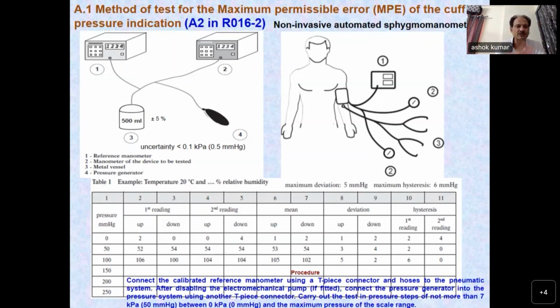If you Google it, you will find the R16.1 and R16.2 PDFs available on the web page. Everybody knows you have to follow all 20 parameters for type approval, including electricals and other parts. So this is one way. Another way is to have the automated device and another reference pressure gauge, with a known volume, like the 500 ml already defined, with plus or minus 5% error or uncertainty, and you can generate the pressure manually and compare the two devices. That procedure is given in R16.1 and R16.2, for either automated or non-automated devices.